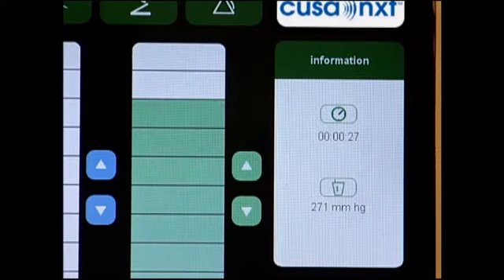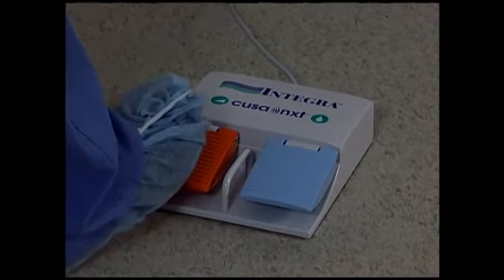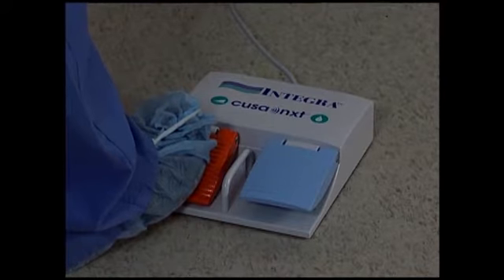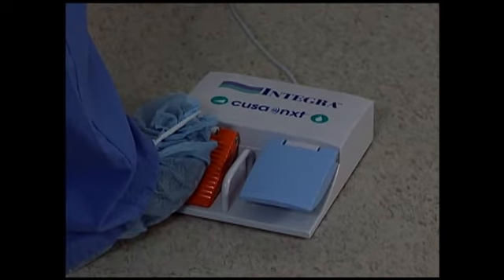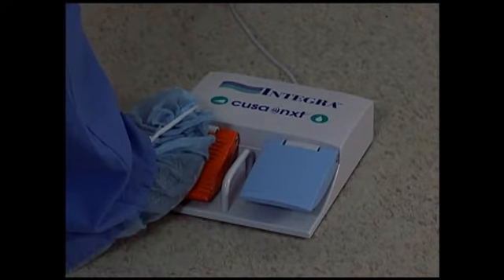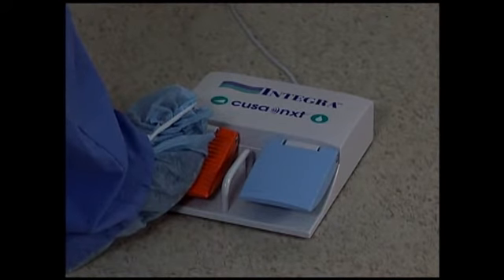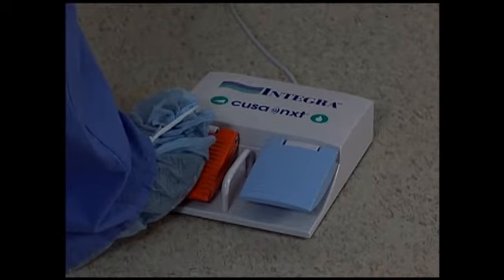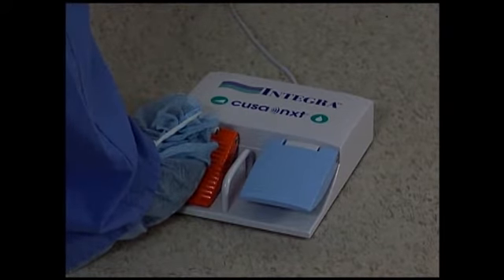The activation timer and system settings will be reset when power is turned off for more than 30 minutes. System settings are retained, however, when the system is powered down for less than 30 minutes, such as during intraoperative MRI imaging. To operate the ultrasonic aspirator, the surgeon depresses the orange power pedal on the left side of the foot switch. The foot switch delivers power proportionally to the distance the foot pedal is depressed.